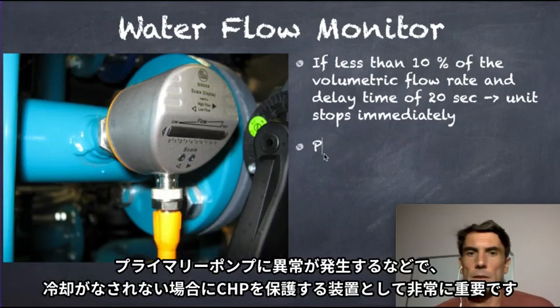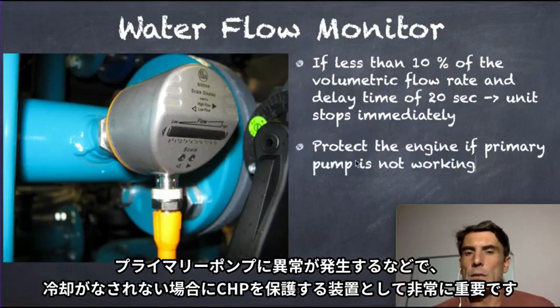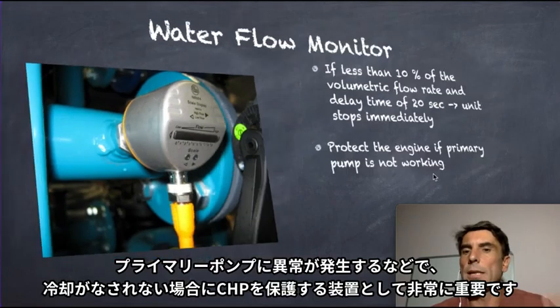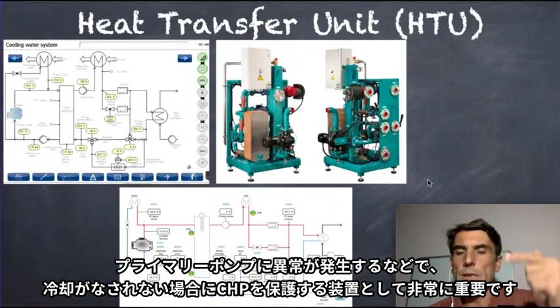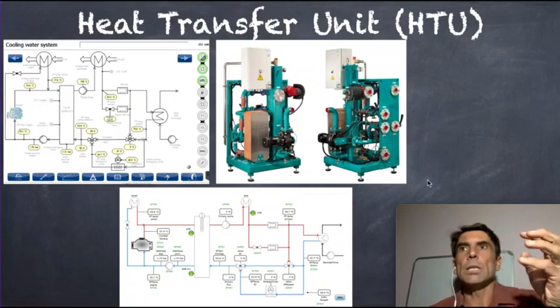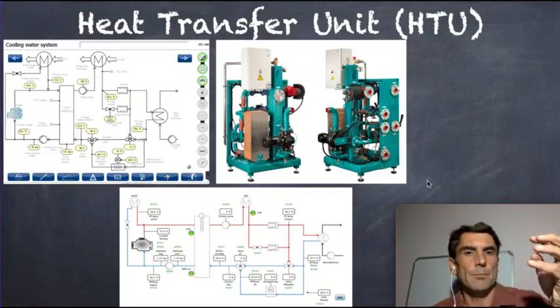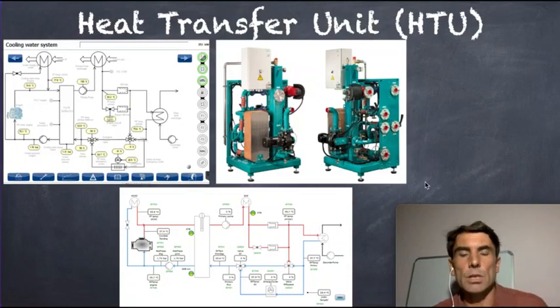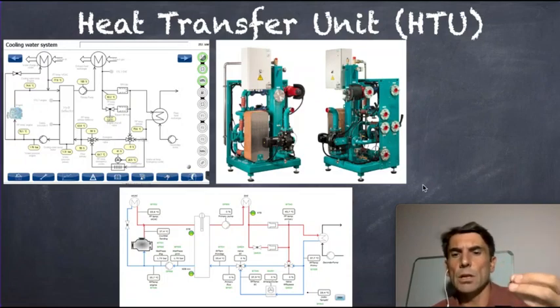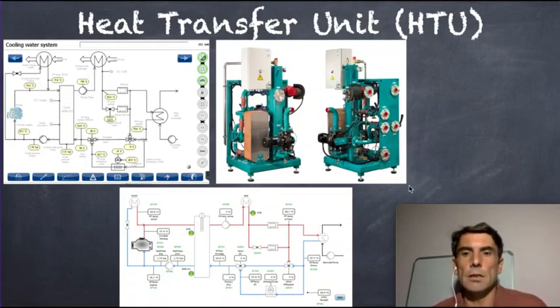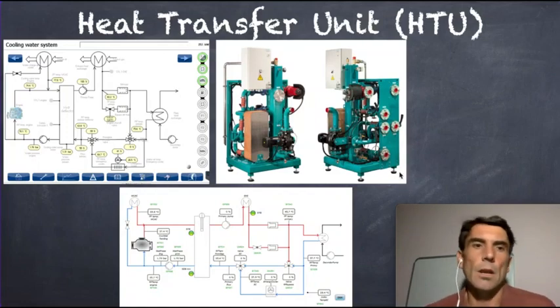So that's important. This actually protects the engine, for example, in case the primary pump is not working, or we do not have enough water flow through the cycle to cool down the engine or keep it on temperature. And if we exceed the temperature and heat up the engine over the limits, we always get issues, other error messages, but we could have damages in the meantime already.